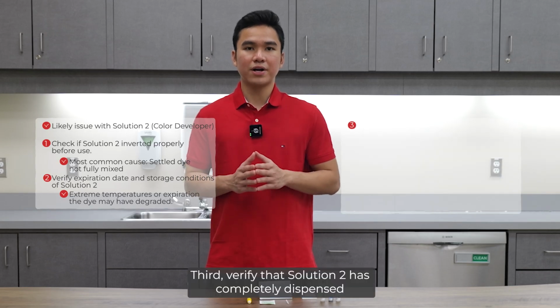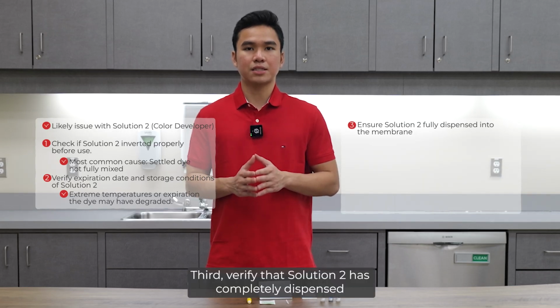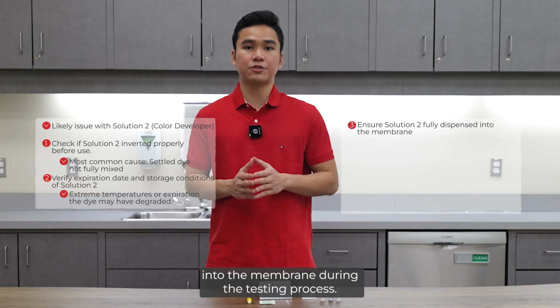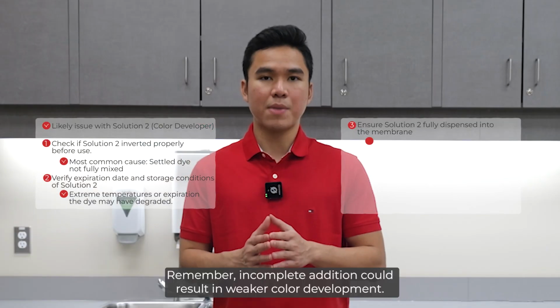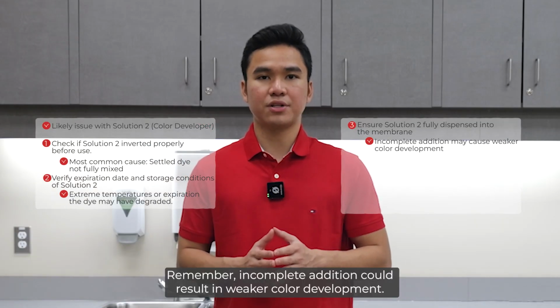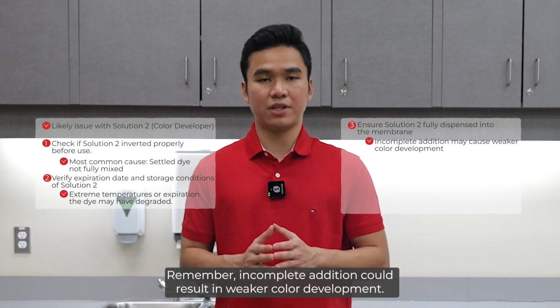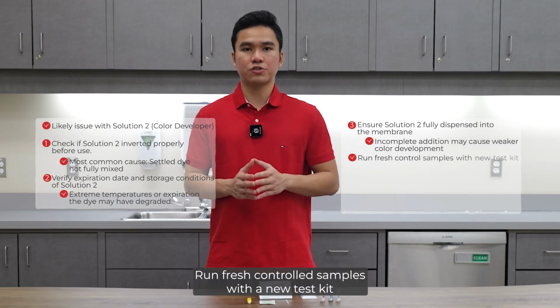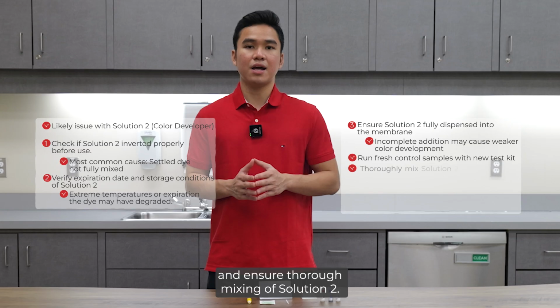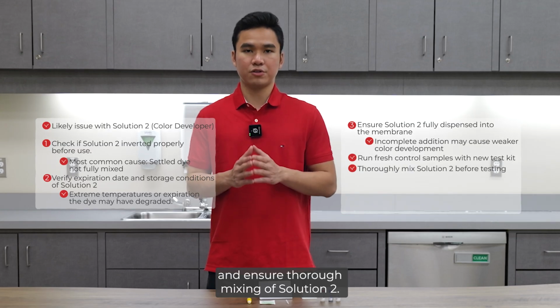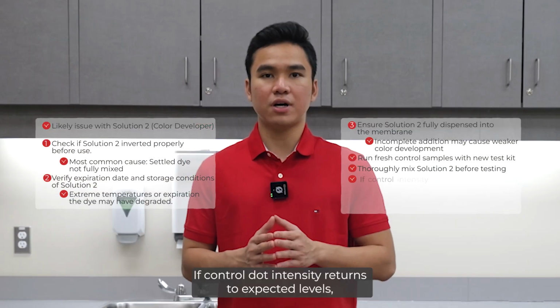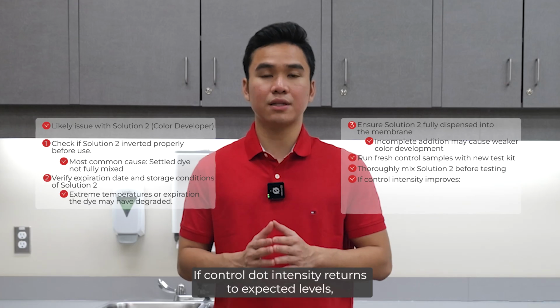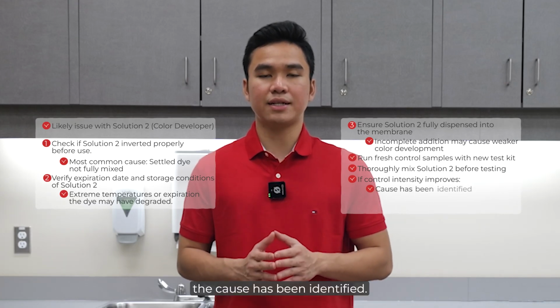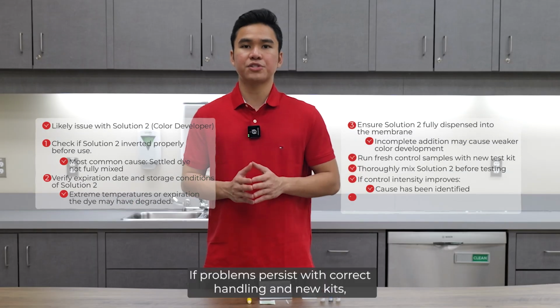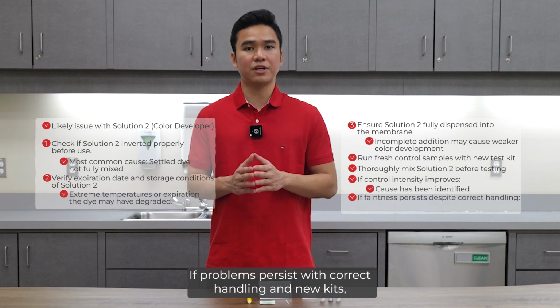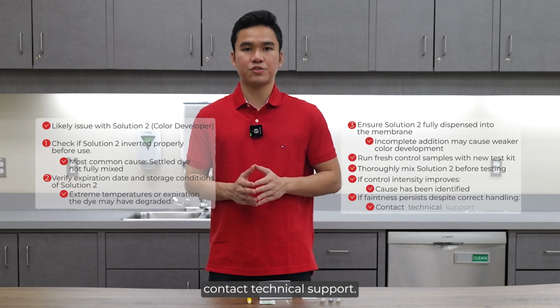Third, verify that solution 2 has completely dispensed into the membrane during the testing process. Remember, incomplete addition could result in weaker color development. Run fresh control samples with a new test kit and ensure thorough mixing of solution 2. If control dot intensity returns to expected levels, the cause has been identified. If problems persist with correct handling and new kits, contact technical support.